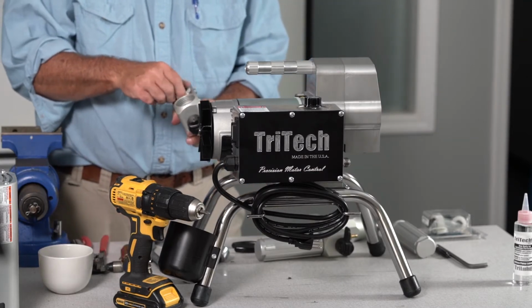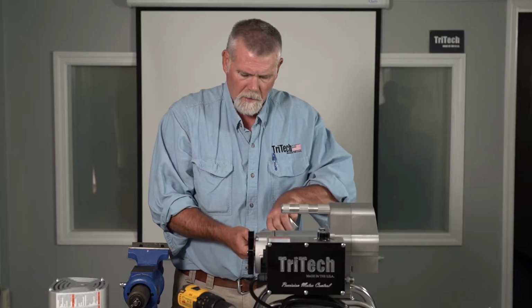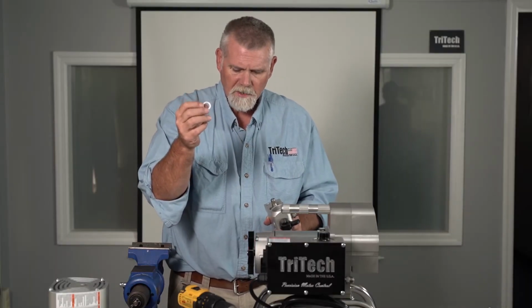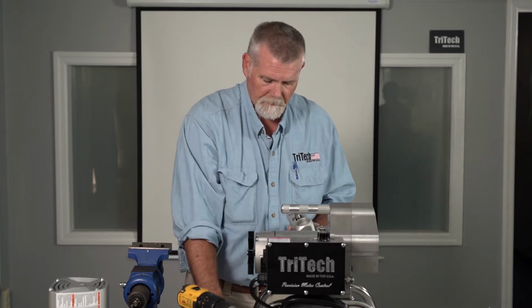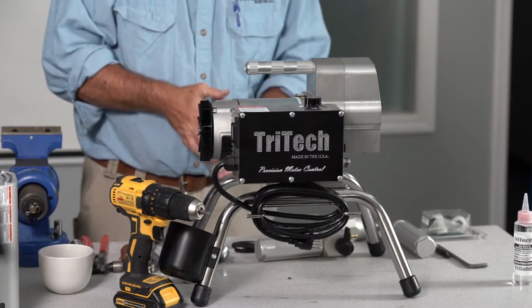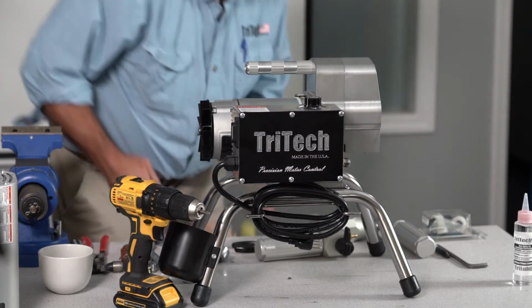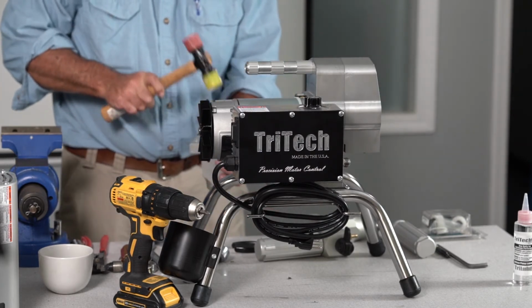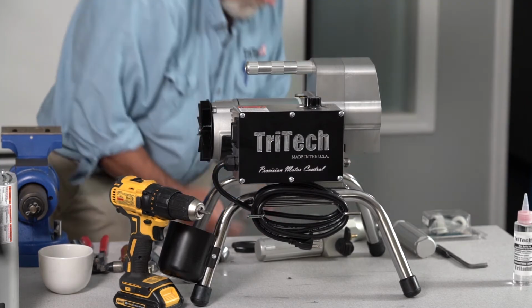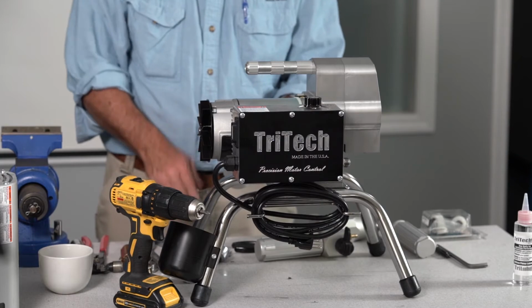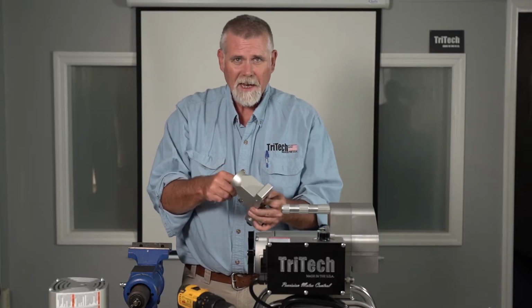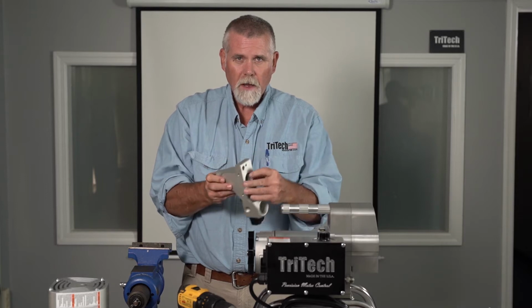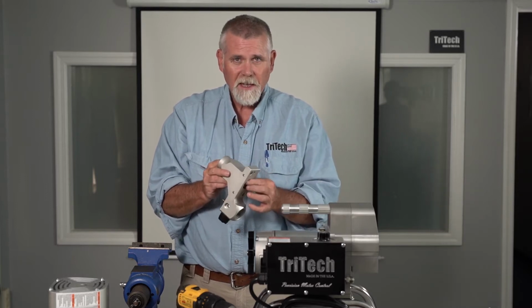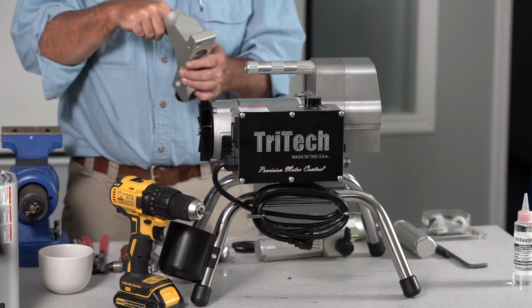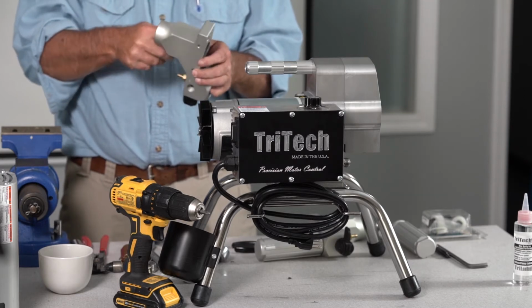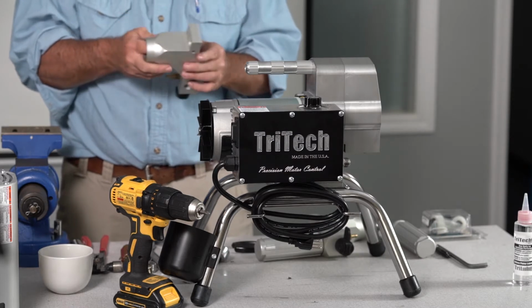We remove our upper packing retainer. And then this is your upper piston guide. This has got to get replaced. Now that that's done, we can knock our piston out. And we want to take a look at our packings while they're still in the pump. You don't want to remove the packings unless you intend to change them. So if there's a cut or a worn mark in both the lower packing or the upper packing, then you know you have to change it.